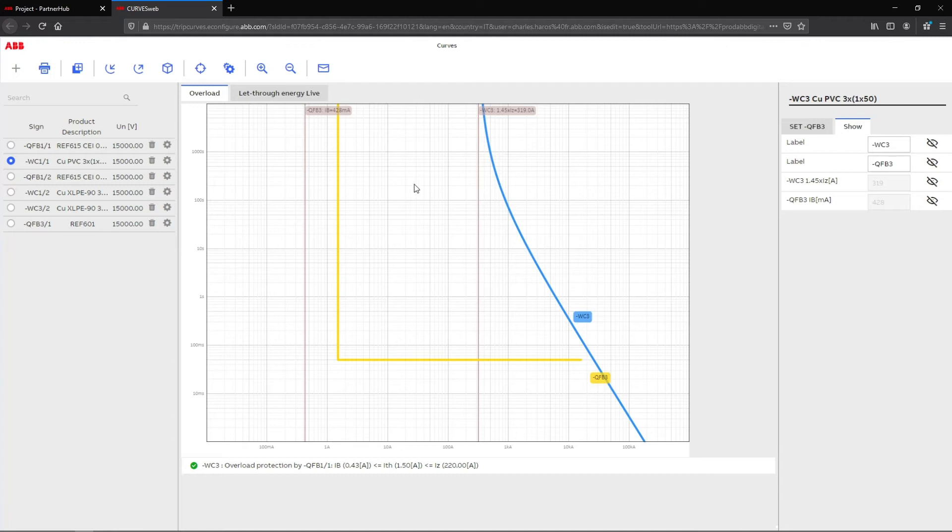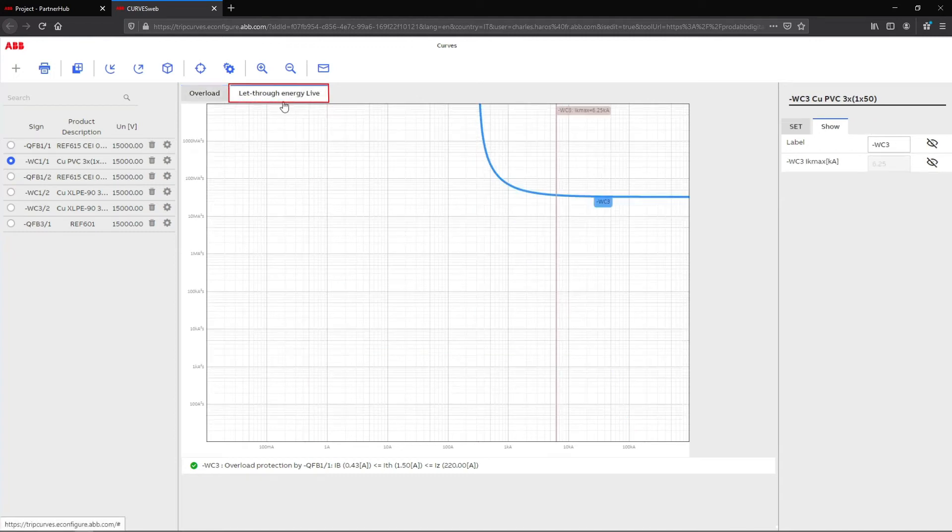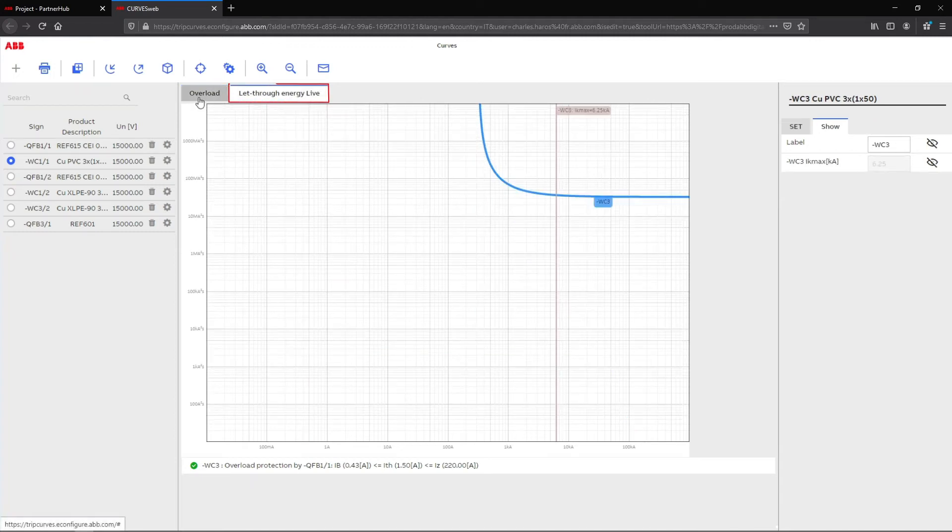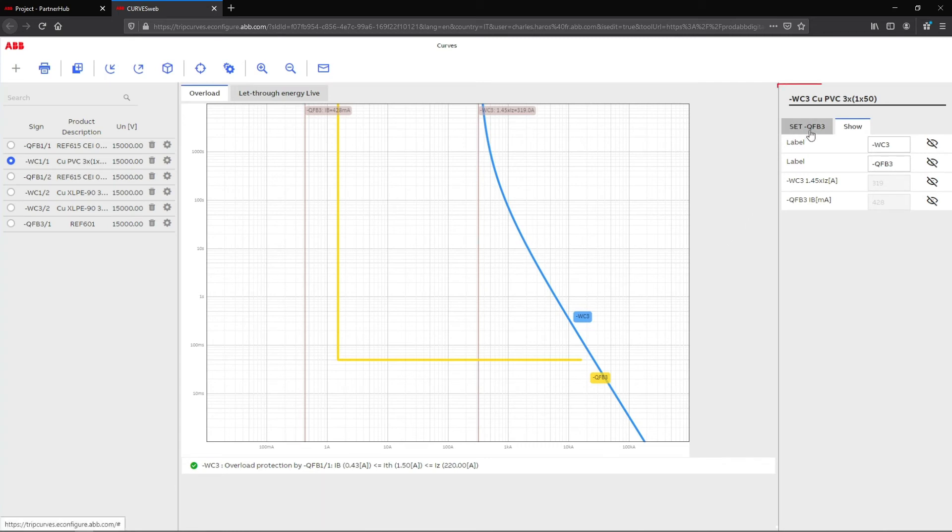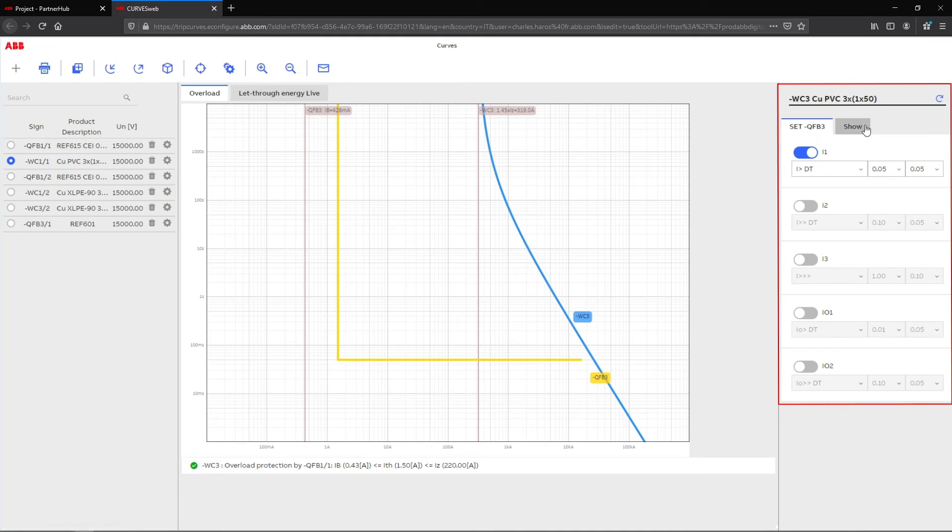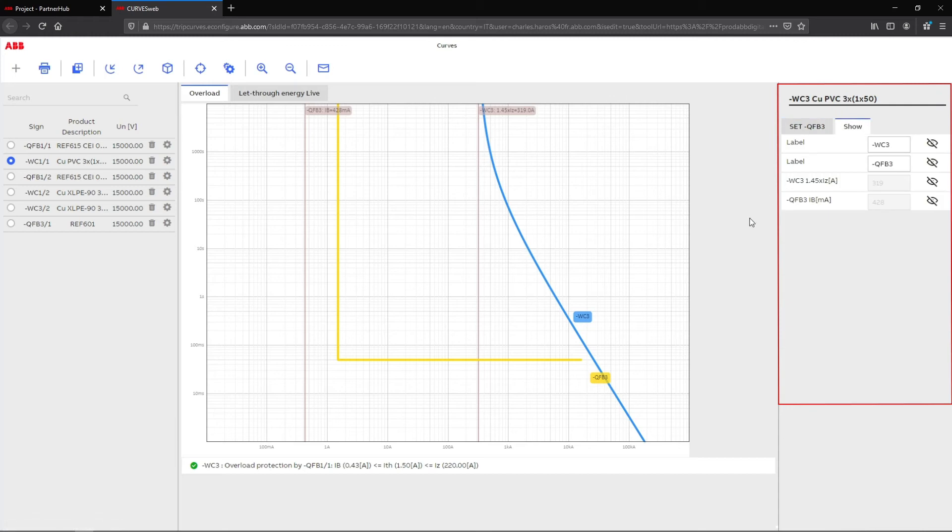For each device, the tab on top displays a different curve according to element type. On the right section of the screen, different threshold levels are displayed for the low voltage breaker or medium voltage relay and fuse protection functions to prevent overload, short circuit, or indirect touch.